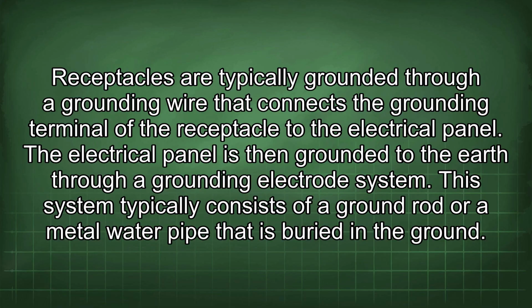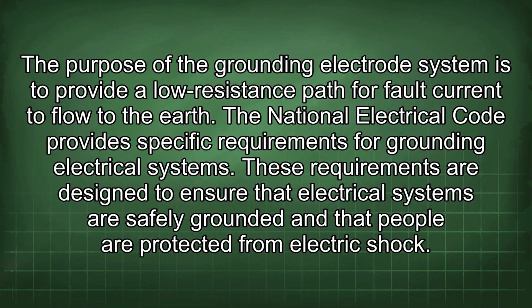Receptacles are typically grounded through a grounding wire that connects the grounding terminal of the receptacle to the electrical panel. The electrical panel is then grounded to the earth through a grounding electrode system. This system typically consists of a ground rod or a metal water pipe that is buried in the ground. The purpose of the grounding electrode system is to provide a low resistance path for fault current to flow to the earth. The National Electrical Code provides specific requirements for grounding electrical systems. These requirements are designed to ensure that electrical systems are safely grounded and that people are protected from electric shock.